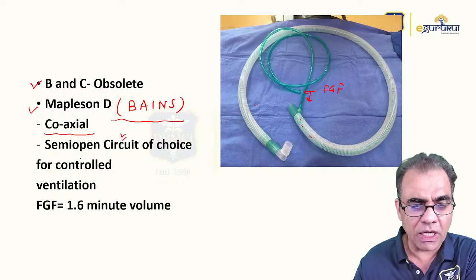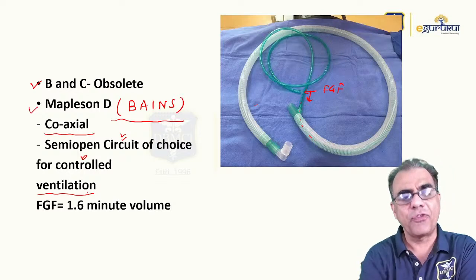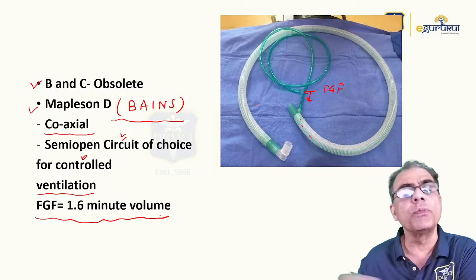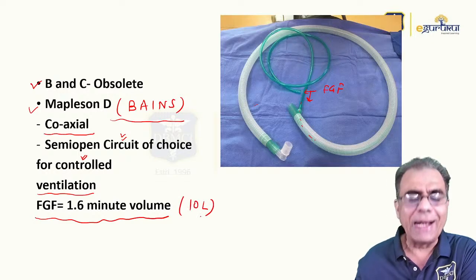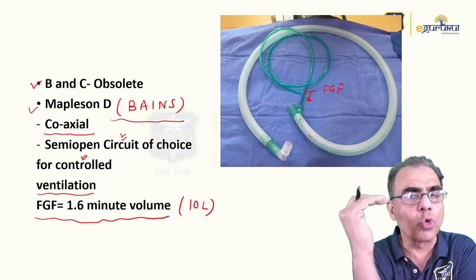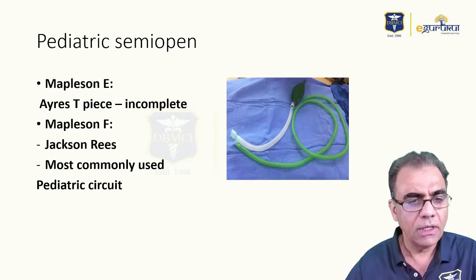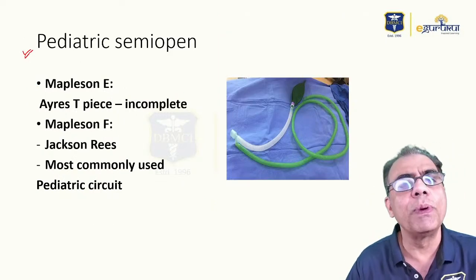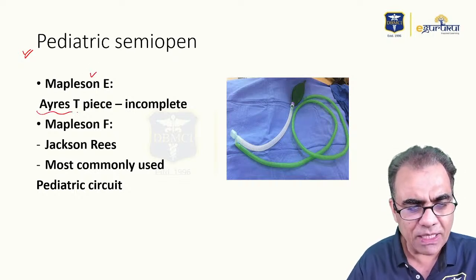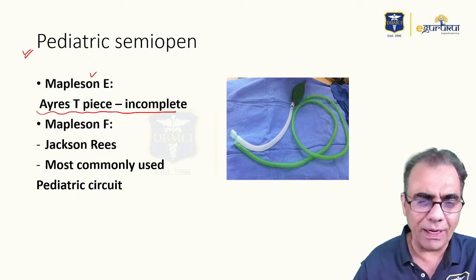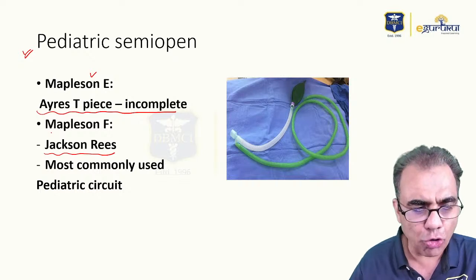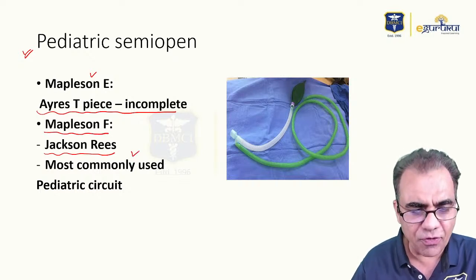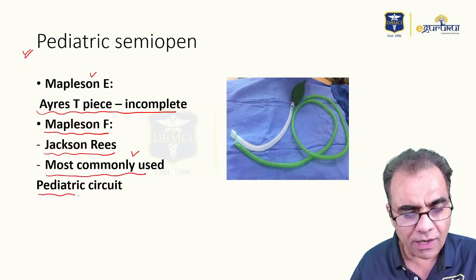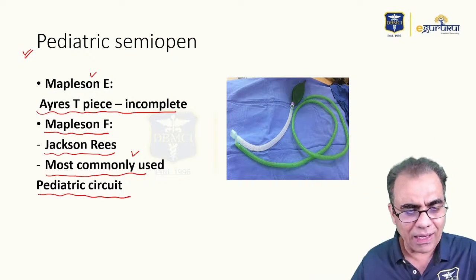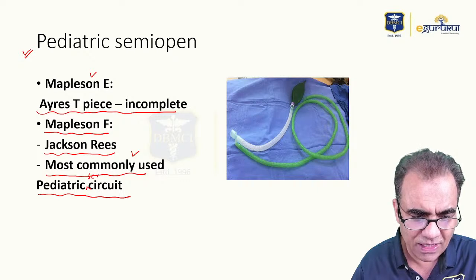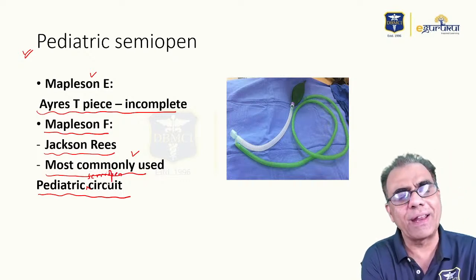And it is the semi-open circuit of choice for controlled ventilation. Fresh gas flow recommendation is 1.6 times the minute volume. 1.6 times the minute volume means around 10 liter flow you have to keep from the anesthesia machine, means through the rotameter. Then the other two pediatric semi-open circuits. Mapleson E was Ayre's T-piece, which was incomplete, but it was made complete by two scientists, Jackson and Rees, which is also called Mapleson F. So Mapleson F, you can say, is the most commonly used pediatric circuit. In fact, this is the only pediatric semi-open circuit, rather I will say.